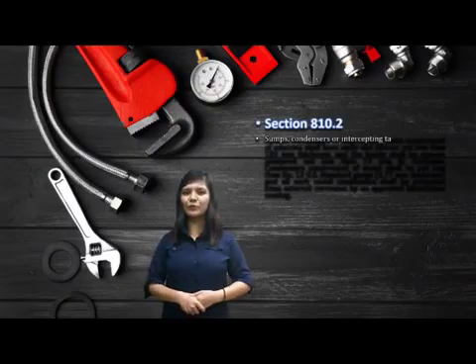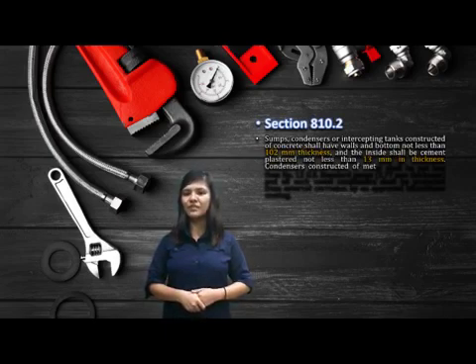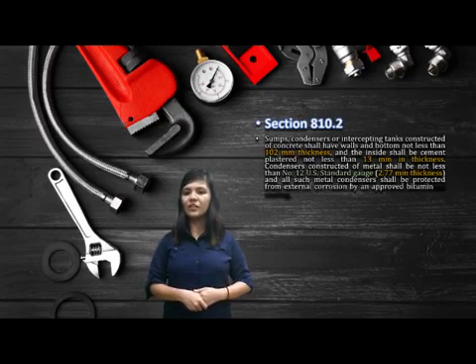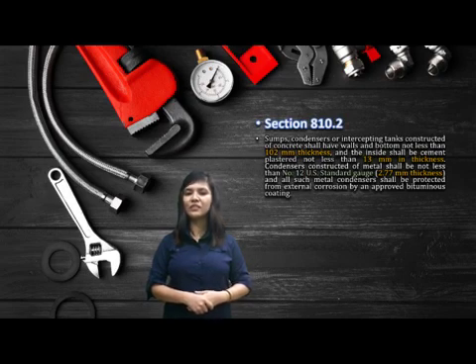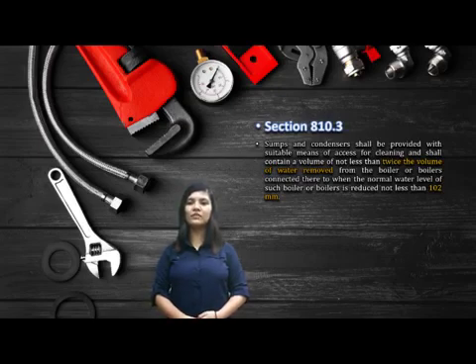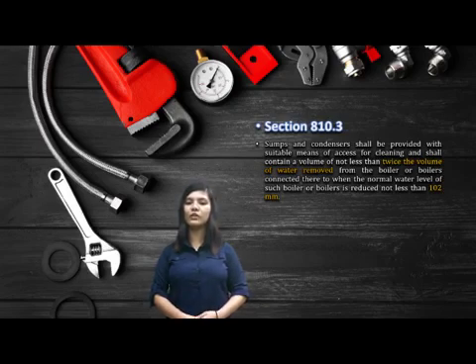Section 810.2: Sumps, condensers, or intercepting tanks constructed of concrete shall have walls and bottom not less than 102 mm in thickness, and the inside shall be cement plastered not less than 13 mm in thickness. Condensers constructed of metal shall be not less than number 12 U.S. standard gauge, 2.77 mm thickness, and all such metal condensers shall be protected from external corrosion by an approved bituminous coating. Sumps and condensers shall be provided with suitable means of access for cleaning and shall contain a volume of not less than twice the volume of water removed from the connected boiler when the normal water level is reduced not less than 102 mm.